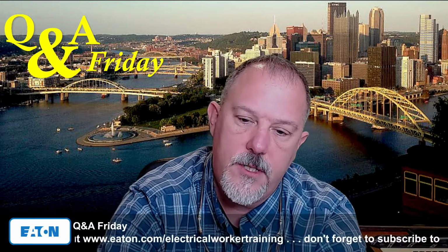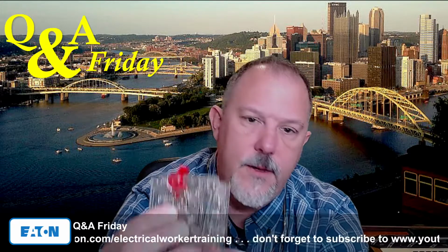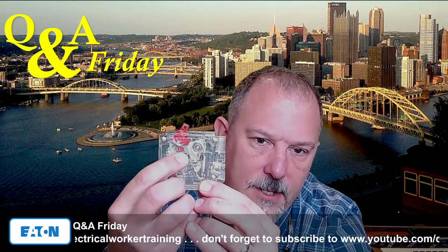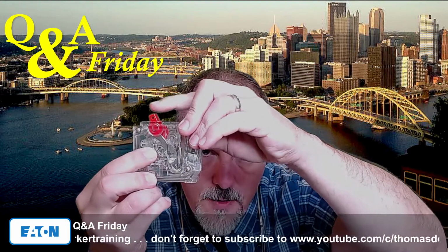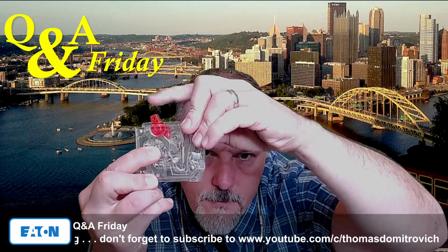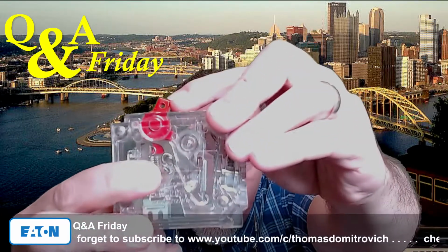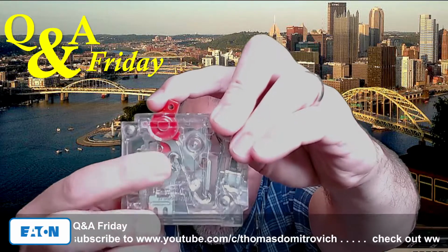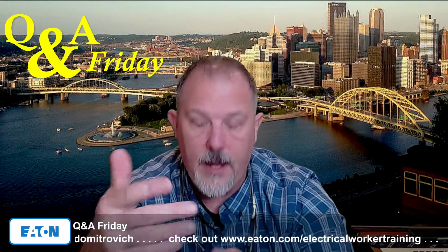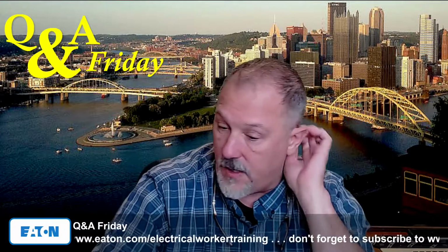Man, I had that backwards. The flexible wire, which is right here, connects the arm. You see it moving, right? Hopefully you see it moving. That flexible conductor connects the contact with the bimetal and your instantaneous, which gives you the thermal magnetic capabilities of a circuit breaker.